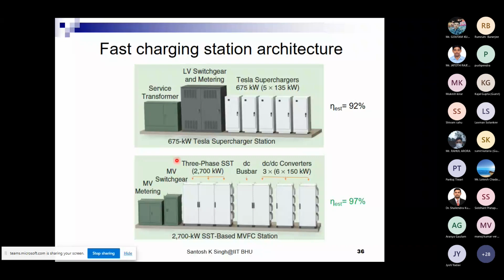This is one fast charging station architecture, and this is the existing one: the Tesla 675 kilowatt supercharger station, making use of 5 units of 135 kilowatts, coming out to 675 kilowatt. This is a low frequency transformer, with our conventional switchgear and metering units. So typical efficiency is around 92% for this particular design.